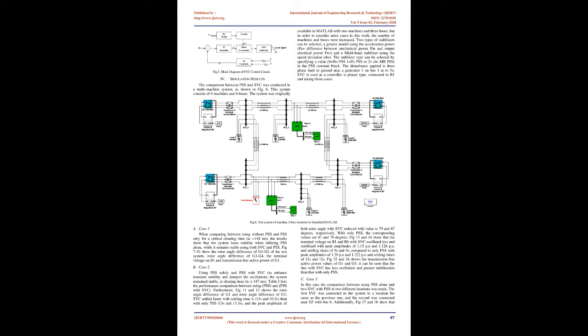stabilizer. The limitations inherent in the other stabilizer structures led to the development of stabilizers that measure the accelerating power of the generator. Due to the complexity of the design, and the need for customization at each location, a method of indirectly deriving the accelerating power was developed, as shown in Figure 2. Fig. 2 Accelerating Power PSS Model. The principle of this stabilizer is illustrated by rewriting equation 1 in terms of the integral of accelerating power, equation 2. The integral of mechanical power is related to electrical power and shaft speed as given below. Equation 3. The ΔPω stabilizer makes use of equation 3.